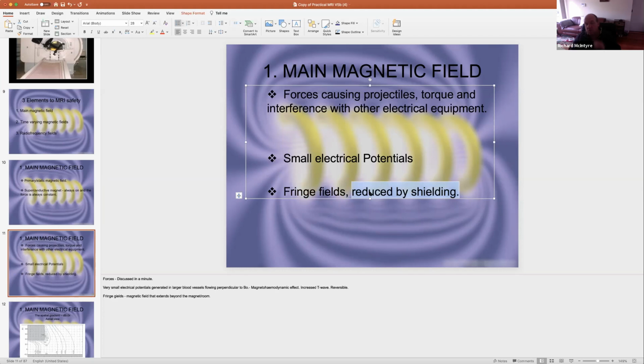We also have what's called shielding. So we have active and we have passive shielding. What shielding does is that it tightens the magnetic field, so we have less magnetic field outside the bore of the magnet. We need the magnetic field to be within the room. If we didn't have shielding, that magnetic field would extend outside into the control area, and obviously that would cause problems with our equipment outside the control area.